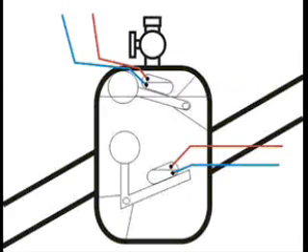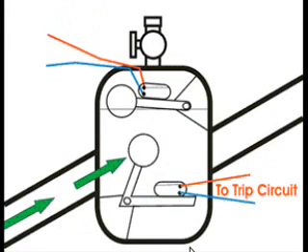More severe types of faults such as short circuit between phases or to earth and faults in the tap changing equipment are accompanied by surge of oil which strikes the baffle plate and causes the mercury switch of lower element to close.